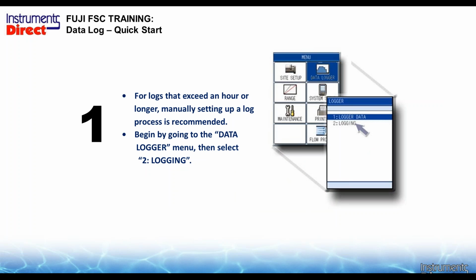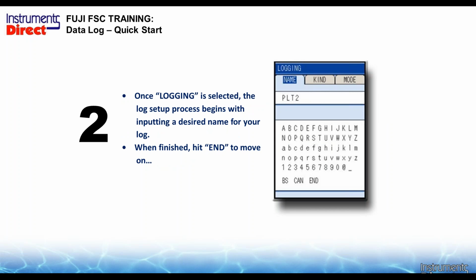If you want to do the traditional log where I want to leave it here for an hour, day, week, month, whatever, in this case I need to go into the meter and set it up. So we begin this by going to the menu and to the data logger menu. Then we select position number 2, logging. Once we're in logging, a next screen will pop up to input your desired named log. Now, this data logger will have an SD card, a 2 to 4 gig SD card, and it will store 25 million data points. So it'll log data until the cows come home.